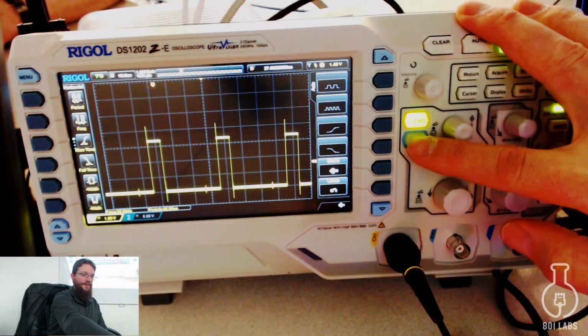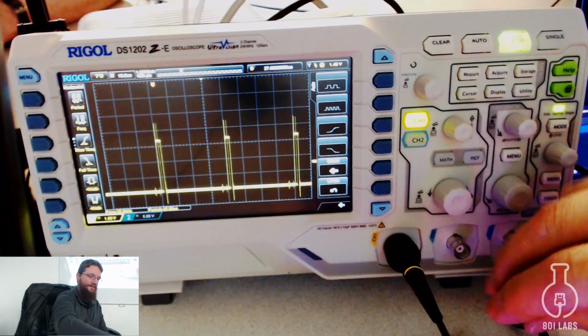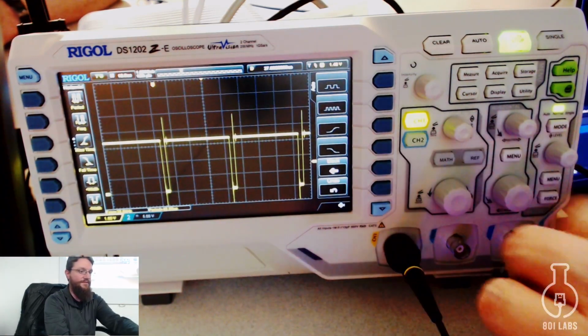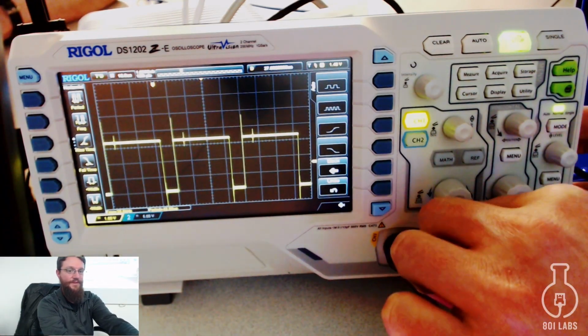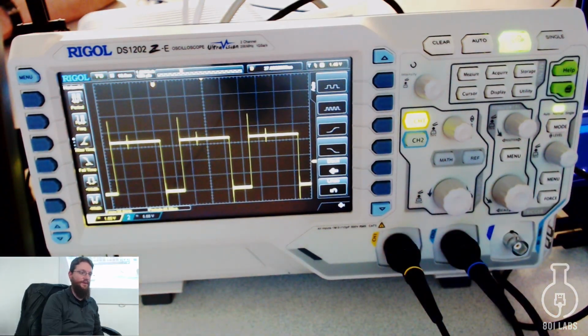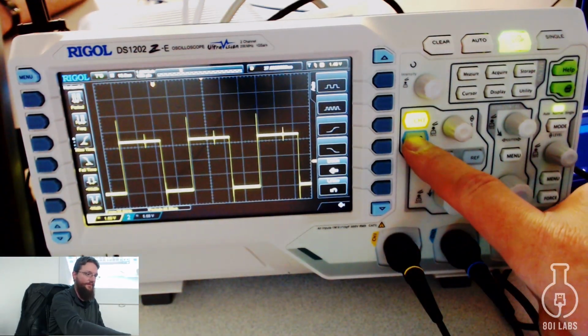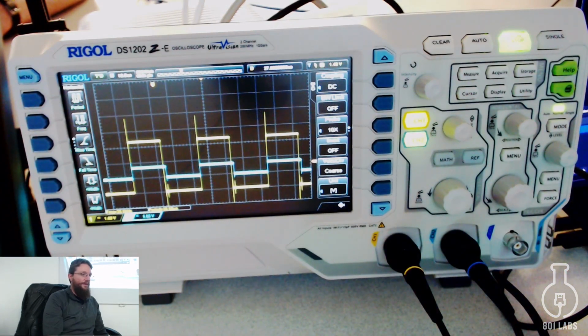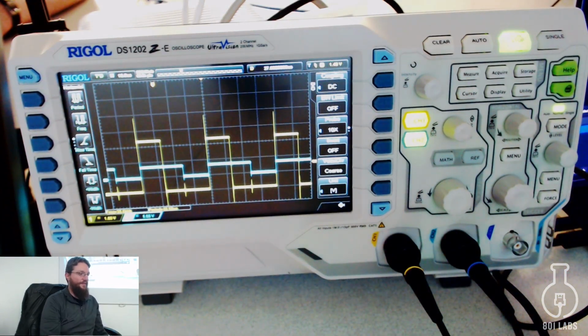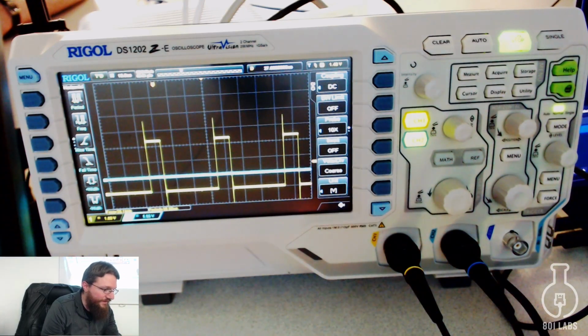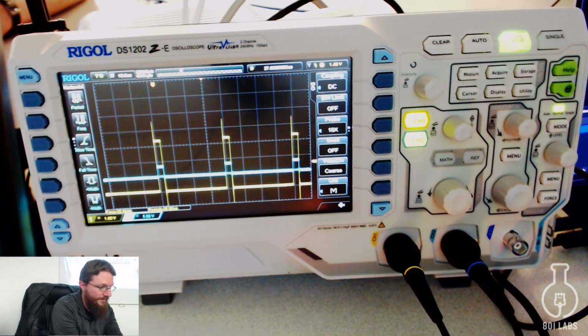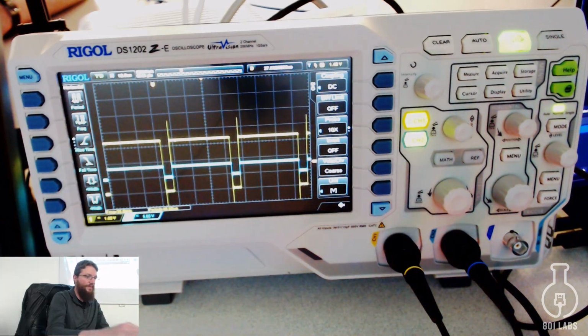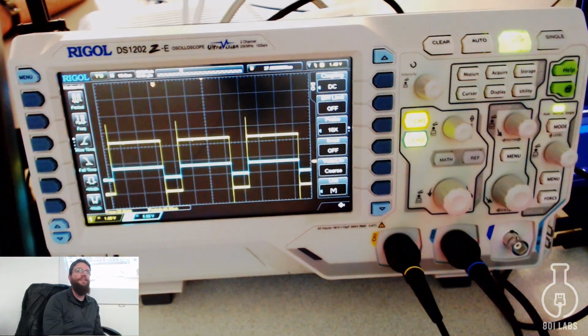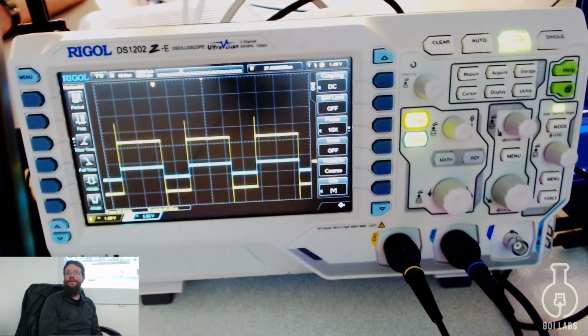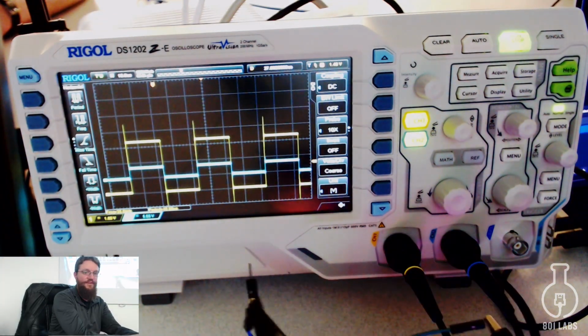If you're measuring more than one signal at once, on this scope, you've got this channel 1 button there glowing green. I will now reconnect the second probe and hit the channel 2 button. So you can see here channel 2, I'm going to put it on the same pin so you can see what's going on. Channel 2 appears in blue on this scope. So both of these are measuring the exact same signal. They're connected to the same pin physically.